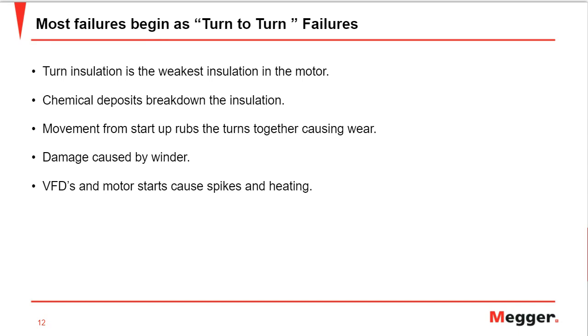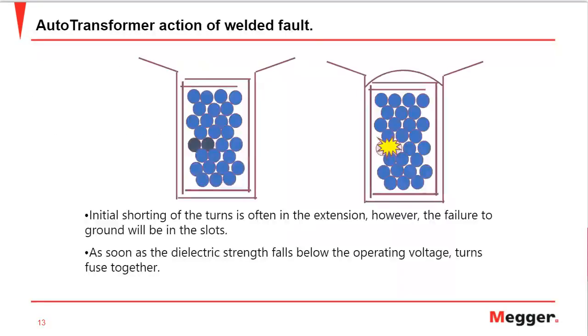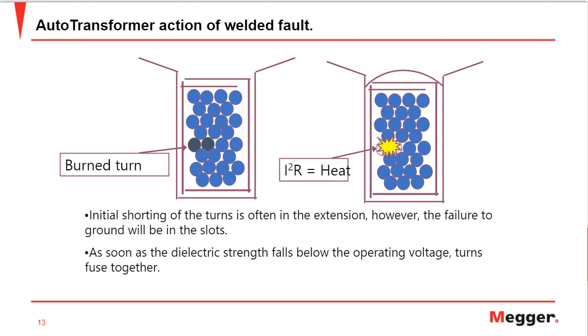We'll see the autotransformer action of a welded fault, and how it relates to today's topic of presentation. When you get a shorted turn, the localized current has another low resistance path to flow, so it's a burnt fault, a burnt turn, and we all know that heat follows current. Heat is a squared factor of current, so the heat generated at that spot would be a squared factor of the amount of current flowing through that fault. For example, let's say there are 16 turns and we get a burnt fault, or burnt turn-to-turn fault.